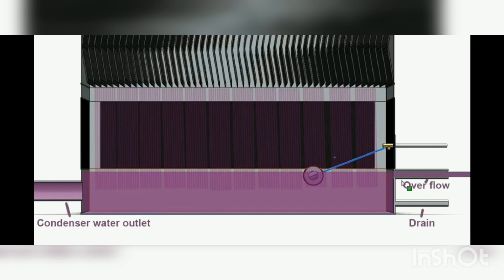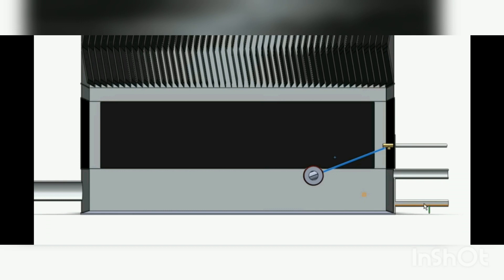The warmer water contains bacteria and salts. As the water evaporates, the water droplets go into the air but the salts remain in the water. These salts collect at the bottom of the basin, and we do not want them sent back to the chiller. That is why the drain pipe is provided — after a certain level of salt accumulation, the drain pipe removes them along with the basin water. The inlet pipe then maintains the water level.